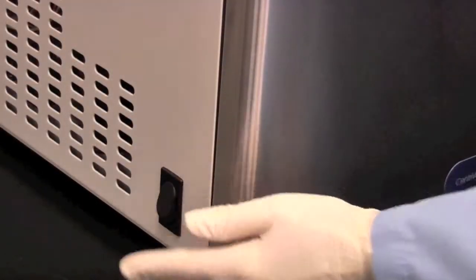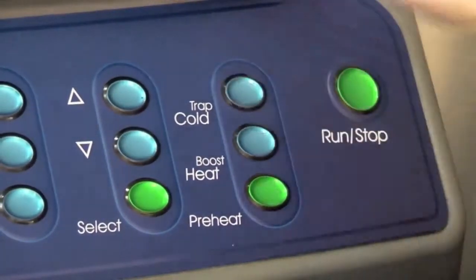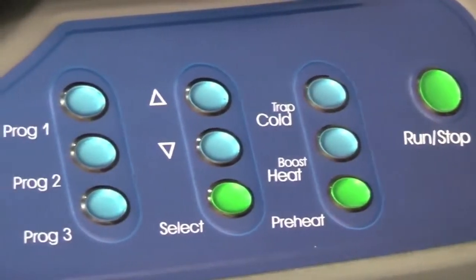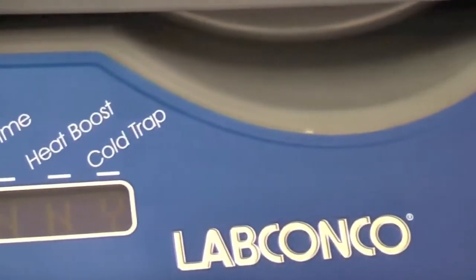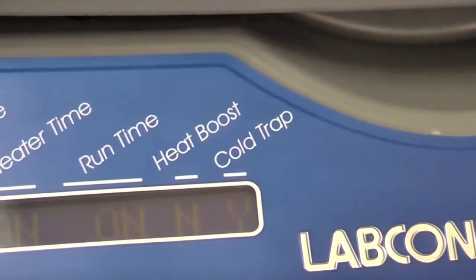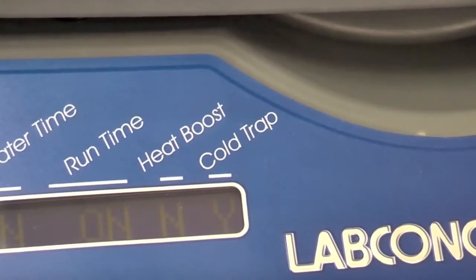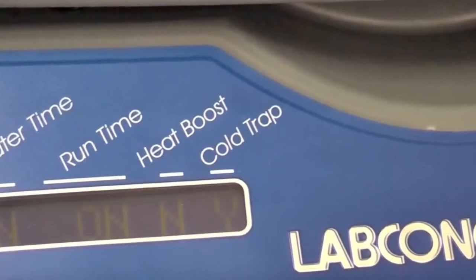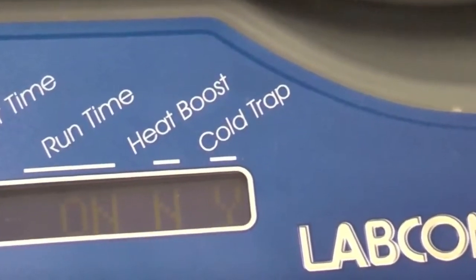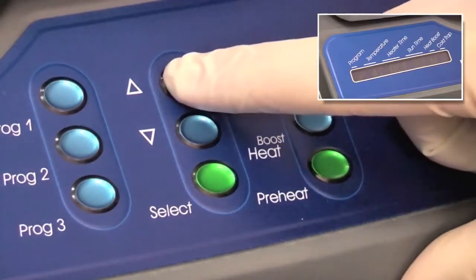Using the CentriVap Complete is simple. Turn the system on and press the cold trap button. When the light goes from blinking to solid, the cold trap is ready. Preheating the chamber prior to evaporation is recommended — select preheat and set it to the desired set point.